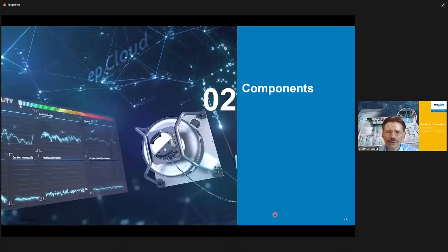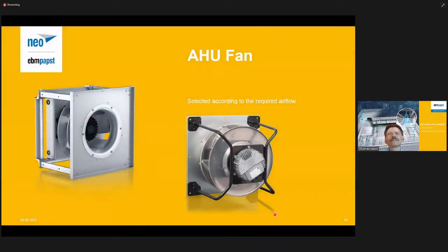Let's jump into components. What are the components that we need to build up such a system? As could be seen, we have an air handling unit, so we need to have fans in that air handling unit that deliver the amount of air that is needed. The typical setup is that you calculate how many people would be in the building, and you design your airflow according to the number of people in the building. That's pretty classical. These fans come in different shapes and types, and they would be the ones installed in the air handling unit.